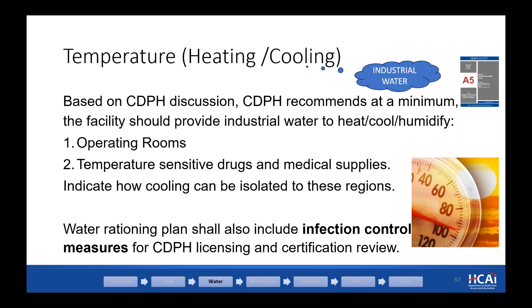There are other alternates, such as air-cooled chillers and DX units, which serve smaller areas. That could be a solution for a few facilities, so that is something to look into. Also, the water rationing plan shall include infection control measures for CDPH licensing and certification reviews, especially when cooling is only limited to these regions, since the temperature can rise beyond the permissible range of, for example, surgical apparatus. The infection control becomes a concern at higher temperature. Again, this is our most current understanding based on the information we have received from CDPH at this moment. If anything changes, we will notify our team, either by updating our A5 guide or through the plan review process.